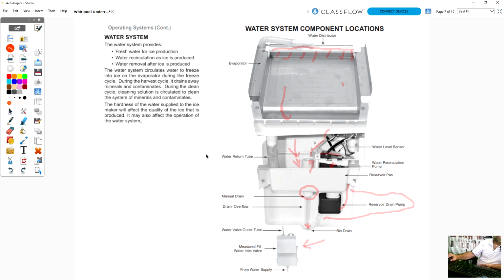We're going to call for water on the water valve, and they said measured fill water inlet valve. It's just a water valve, but the water level sensor here is what's telling the unit how much water's in there, so that's why it's called a measured fill water valve. And it'll fill our reservoir up. Once the reservoir fills, it'll shut the valve off and turn on our recirculation pump and our compressor and our condenser fan. Water starts circulating over the top of the evaporator, and because this evaporator is running 15 degrees below zero like a refrigerator, the water is going to start to stick to it as it freezes.